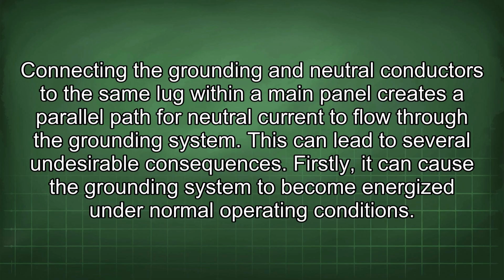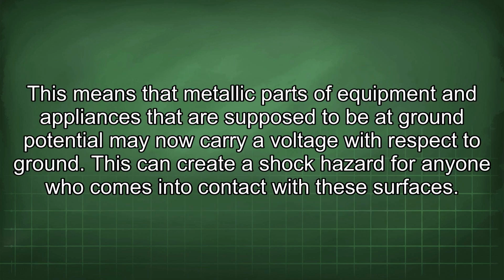Connecting the grounding and neutral conductors to the same lug within a main panel creates a parallel path for neutral current to flow through the grounding system. This can lead to several undesirable consequences. Firstly, it can cause the grounding system to become energized under normal operating conditions. This means that metallic parts of equipment and appliances that are supposed to be at ground potential may now carry a voltage with respect to ground. This can create a shock hazard for anyone who comes into contact with these surfaces.